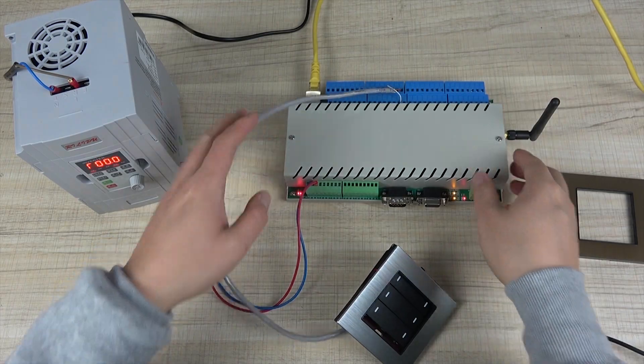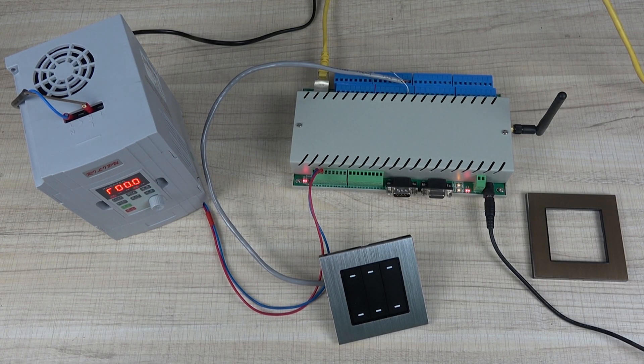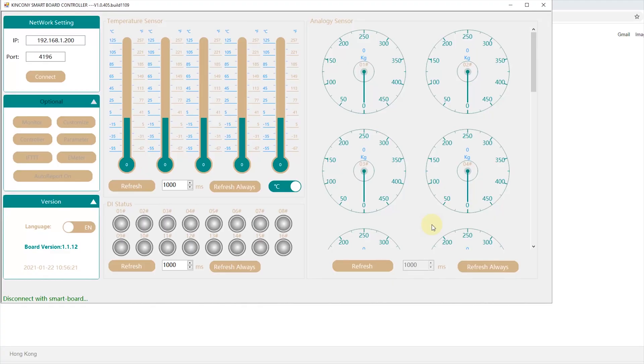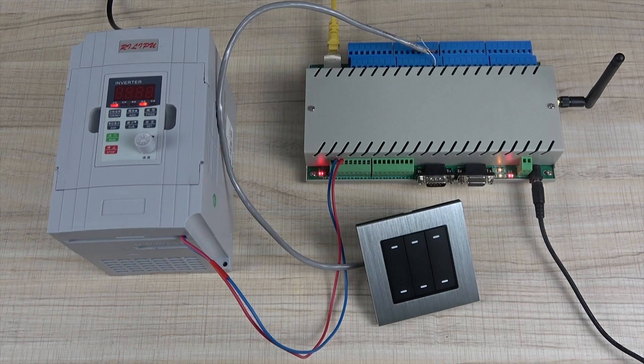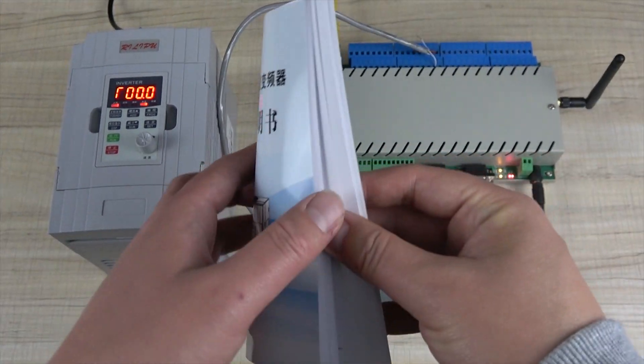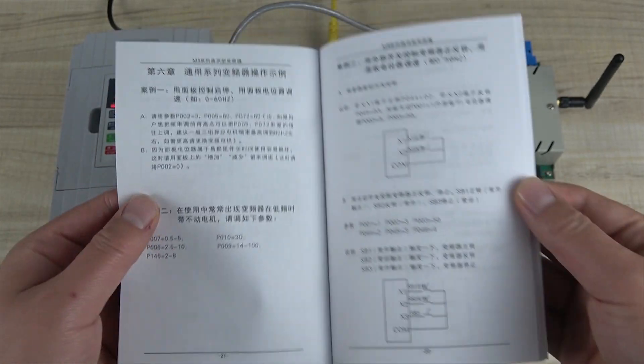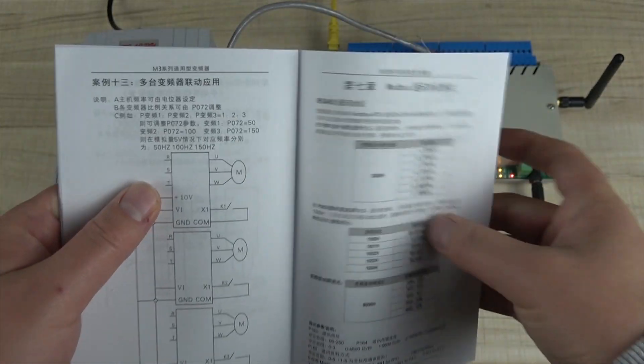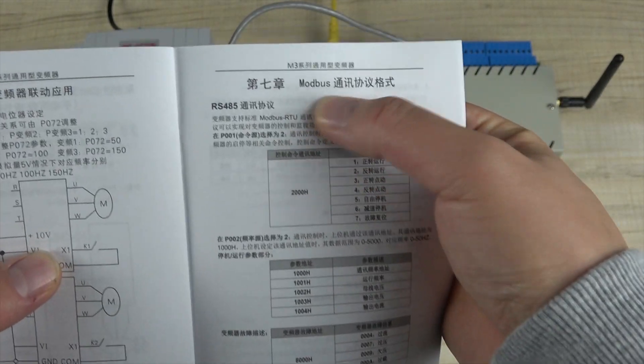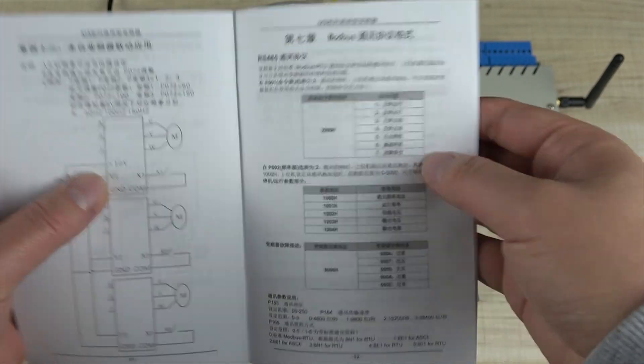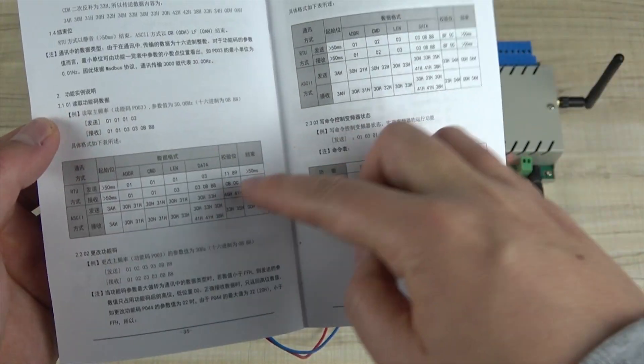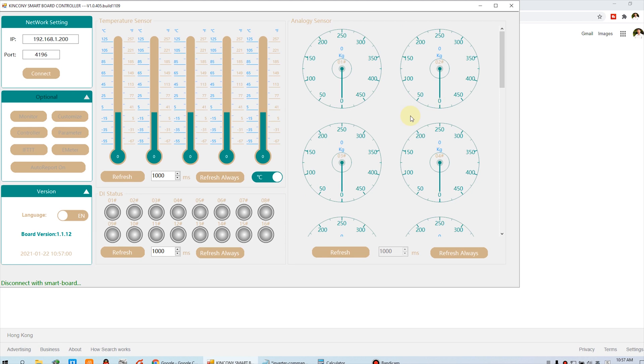Okay, this is the hardware. Now we begin to use the PC software to configure how to work. Before using this PC software, you should find out the manual of the inverter. You need to find out the protocol of the inverter — just like this. Usually the inverter uses the Modbus protocol. So you can find your inverter's manual and find the commands — how to start, how to stop, and how to change the frequency. I have already saved these commands on my computer, so it's easy for us to test.